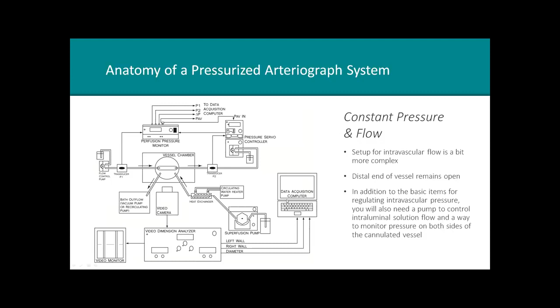Finally, I want to talk about the parts of a pressure arteriograph. This is a current generation arteriograph we make here at Living Systems, showing the different parts of the system. Looking down on the vessel chamber sitting on the stage of a microscope—most times an inverted microscope is used, so there's an optical cover slip that allows the objective beneath the chamber to image the blood vessel.